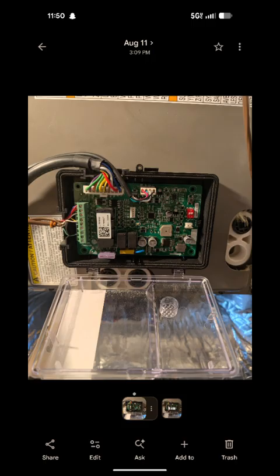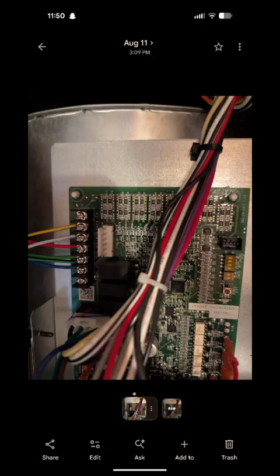Some units come with their A2L sensor in the wrong spot from the factory. This one, for instance, came with the sensor in the drip line of the condensation in the coil, mounted to the coil. Water drips in there after running for an hour or so, especially if you have a really good charge and it's cooling really well, and it ends up ruining your sensor. Luckily with this one, we were able to dry the sensor out and get it going.